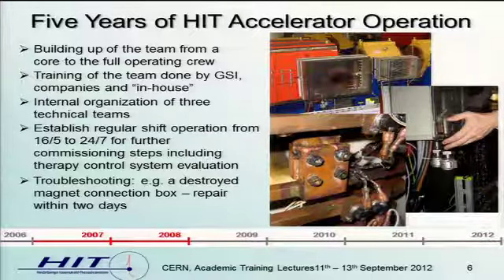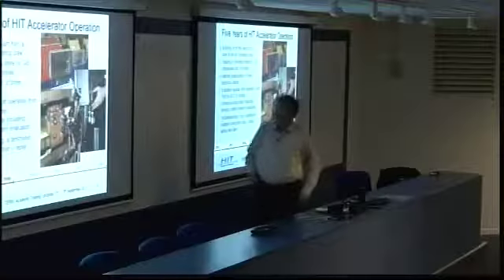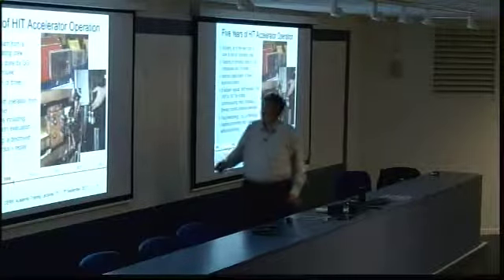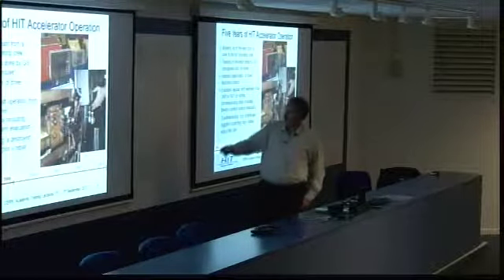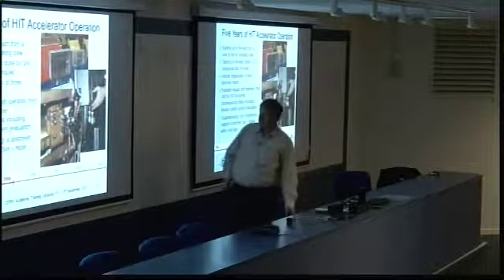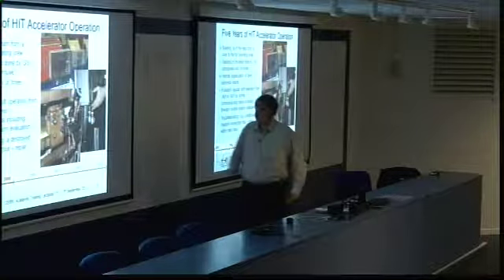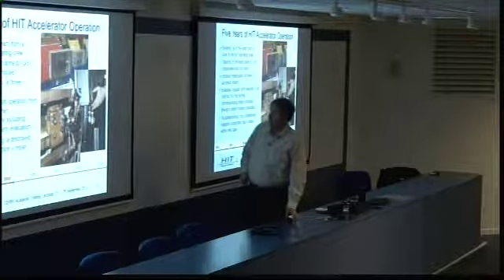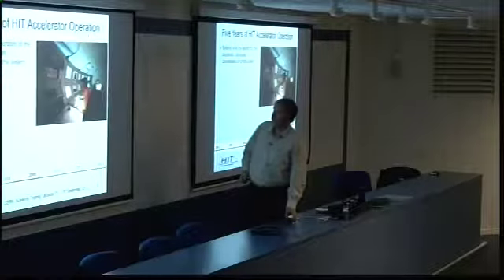So you can see a destroyed magnet connection box here, which burned. But such a magnet box is a nice thing because you have water and current in, so when the hose is burned, the water comes out and they are self-extinguishing. So you see the water comes out, so we have to repair such troubleshooting things also, and we got this within 2 days, so there was no big break in the commissioning.